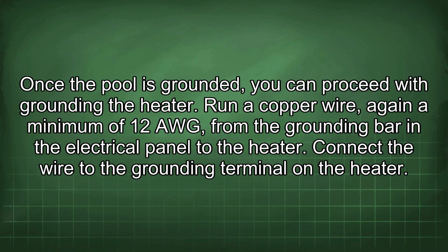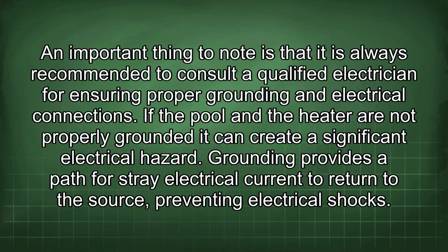Once the pool is grounded, you can proceed with grounding the heater. Run a copper wire, again a minimum of 12 AWG, from the grounding bar in the electrical panel to the heater. Connect the wire to the grounding terminal on the heater. An important thing to note is that it is always recommended to consult a qualified electrician for ensuring proper grounding and electrical connections. If the pool and the heater are not properly grounded, it can create a significant electrical hazard.